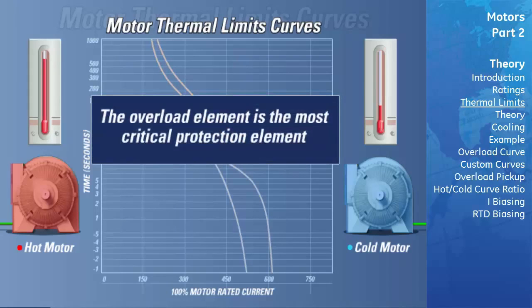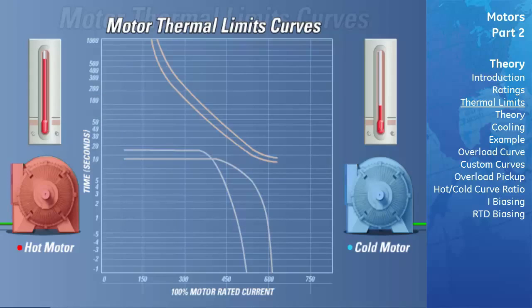The relay's overload element is the main protection element and is the most critical to motor protection — it is always active and cannot be shut off. Motor data sheets should be supplied with every motor. Part of this data should be a thermal limit or thermal damage curve, which indicates the amount of time a specific amount of current can be supplied to the motor without damaging it. The cold thermal limit curve indicates the amount of overload current the motor can withstand before damage will occur when the motor is cold, at the ambient design temperature, which is normally no greater than 40 degrees Celsius.